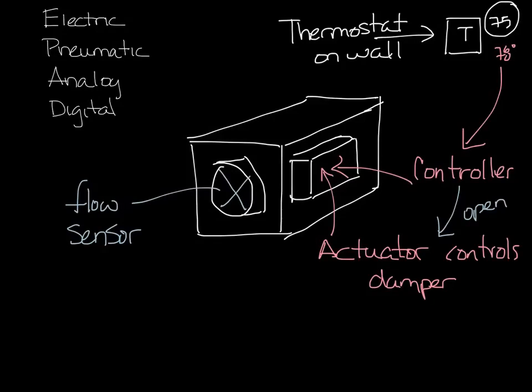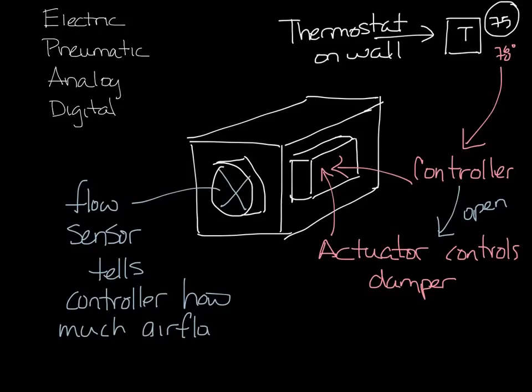This whole time the flow sensor is measuring the air flow in the box so that it gets the right amount of air flow regardless of what the pressure is in the system itself. So that's a super simplified view of the operation of the controller, actuator, flow sensor and thermostat. Obviously you can have reheat and other things controlled by the controller but that gives you the basic idea.